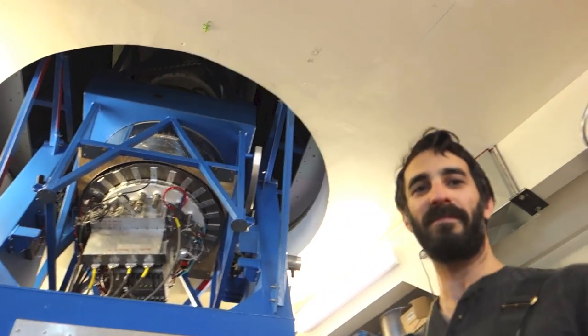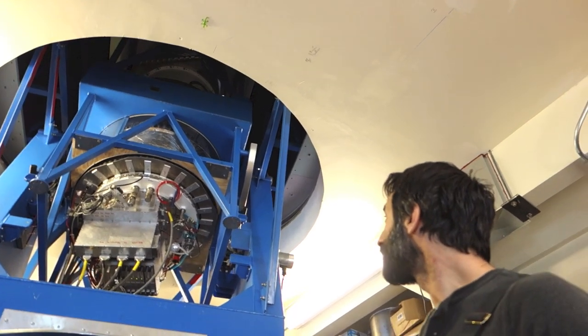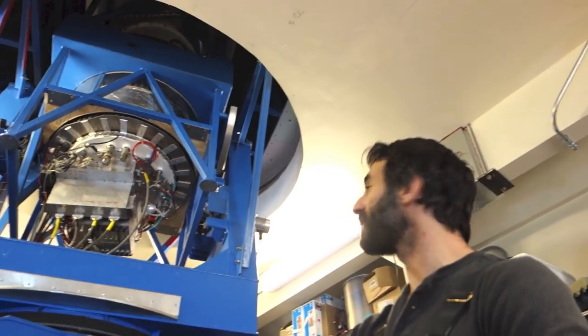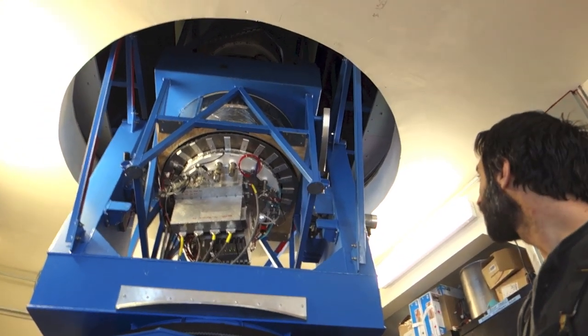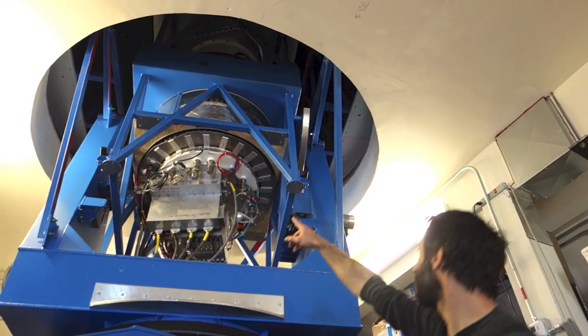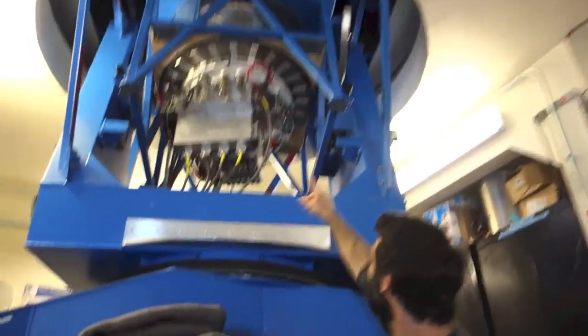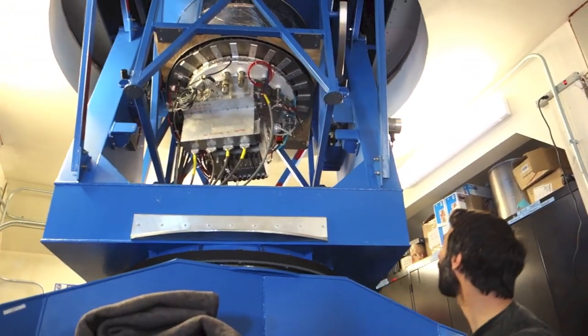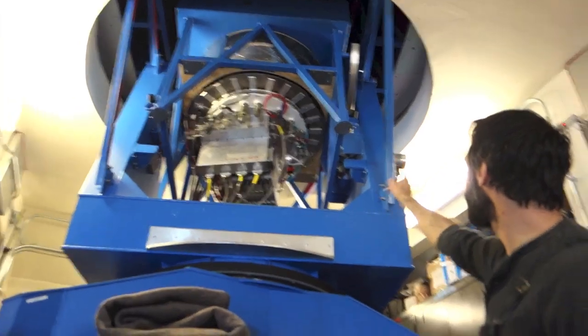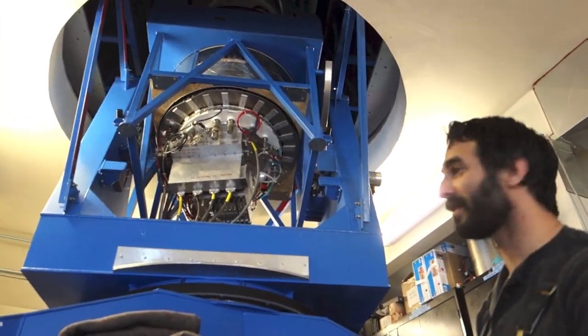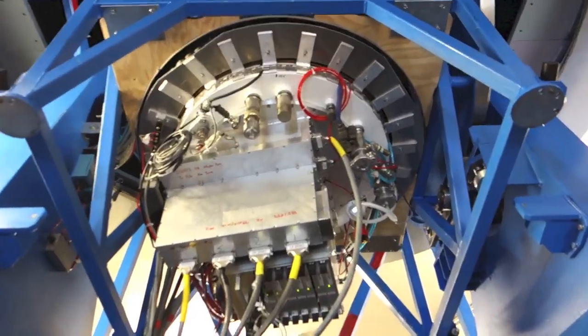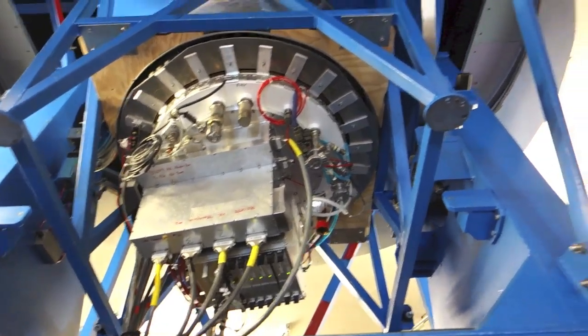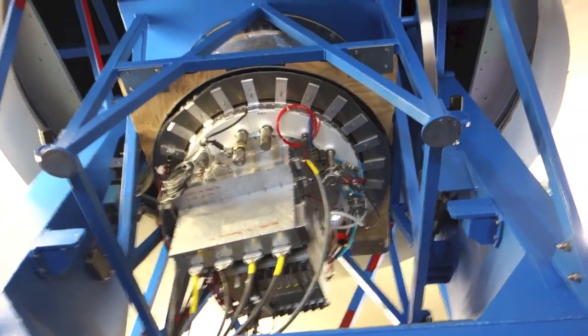What about the cooling system for the cryostat? It's a liquid helium cooled system which we recharge about every three days. You can see the fill port in the back there, followed by the vent port. The blue and white vents lead to our liquid helium readout sensor, so we know the flow rate, and there's a level sensor as well to figure out exactly how much we have left.